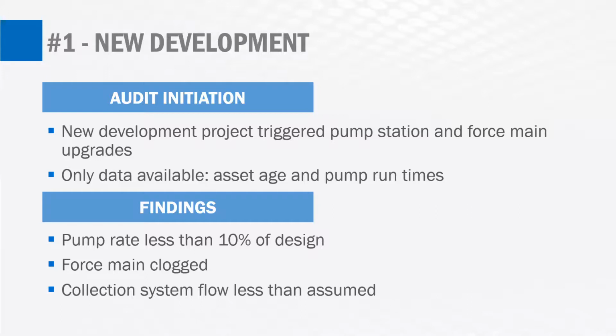The audit was performed for this station, running through many of the steps that Marco just went over. It turns out that through the drawdown testing, it was found that the pumping rate was less than 10% of the design rate, which was very eye-opening. The design flow rate was 300 gallons per minute for this station, and the drawdown results were 30 gallons per minute. It was also found through hydraulic analysis that the force main was clogged, and it was recommended that the force main be cleaned.